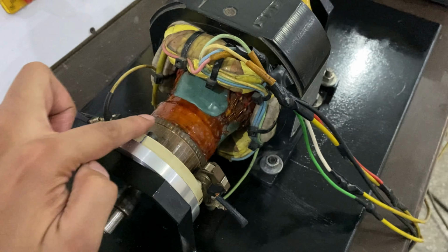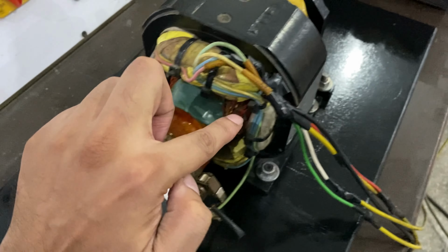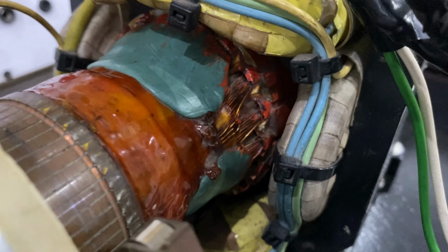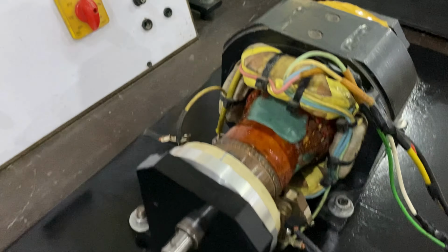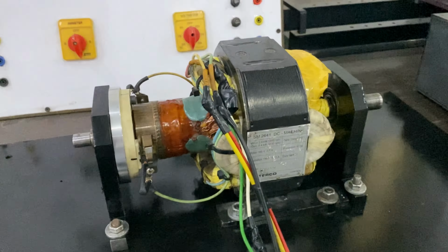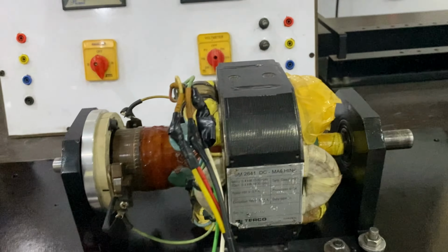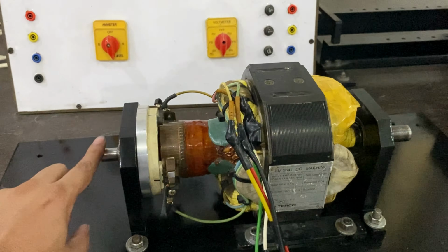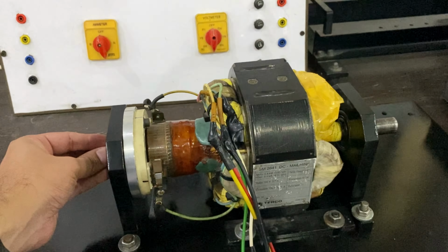Your armature is the rotating part. The armature core is there inside. If you look at it inside, here you can see some slots. The armature winding is placed over there, the end terminals are over here on the commutator segments, then the carbon brushes, and this armature is suspended in the magnetic field. For that you can see this shaft. There are bearings over here, one bearing over here and one bearing, as you can see, over here.